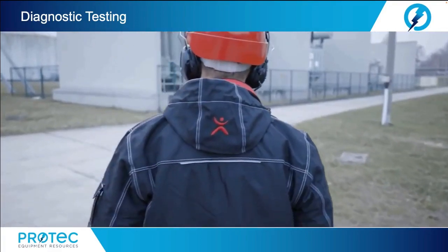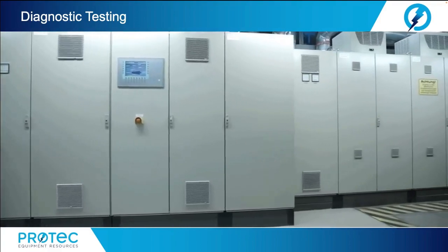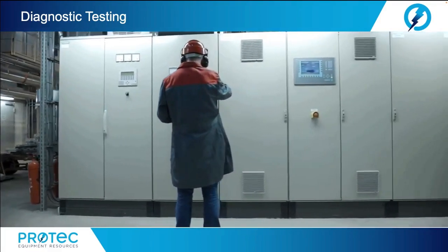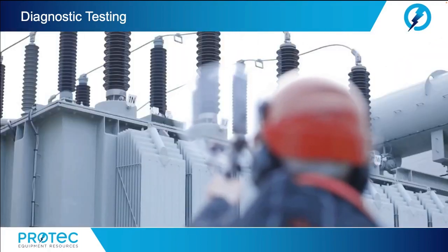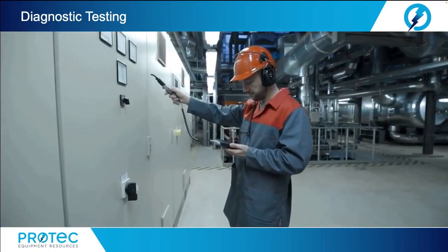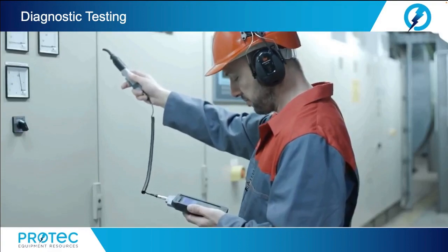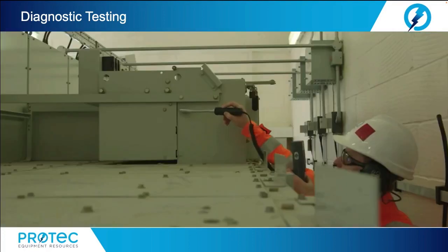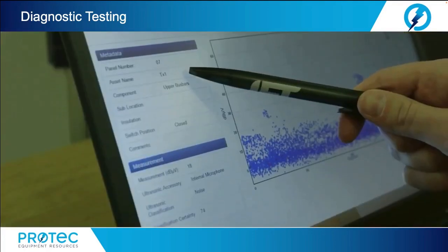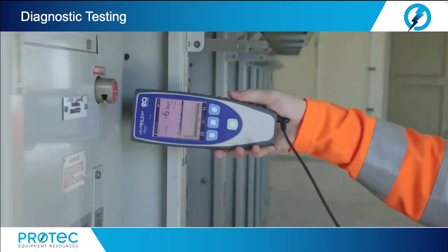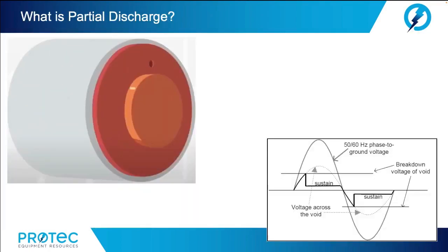Now, partial discharge testing plays a critical role in determining the health of electrical assets and ensuring maximum uptime. Partial discharge testing provides reliability managers with the critical information to target maintenance resources to the areas that require attention. As with any diagnostic technology, however, an understanding of the technology and a logical approach to implementation is necessary to render an effective program. Now, partial discharge is a localized electrical discharge that only partially bridges the insulation between conductors and which can or cannot occur adjacent to a conductor. Now, this was a quote taken directly from the IEC 60270 document.